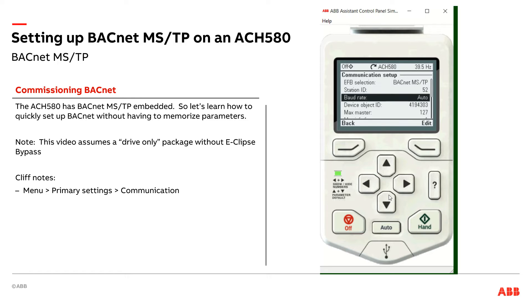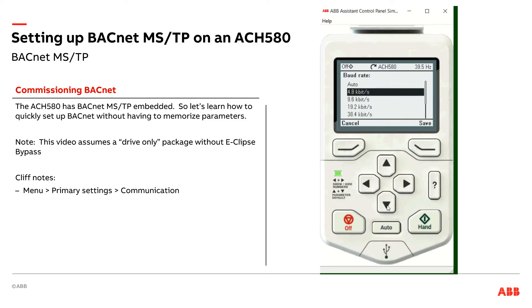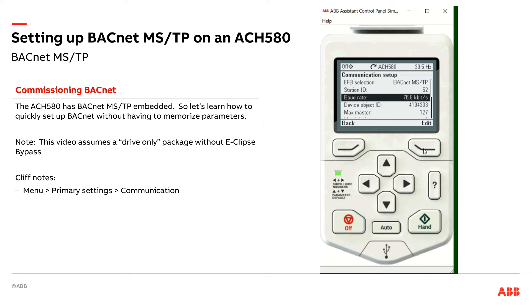You can set the baud rate. The ACH 580 does have auto baud detection, so usually I use that. But if I happen to know — which the controls contractor will know — what the baud rate is, let's say it's faster at 76.8, go ahead and set that up.